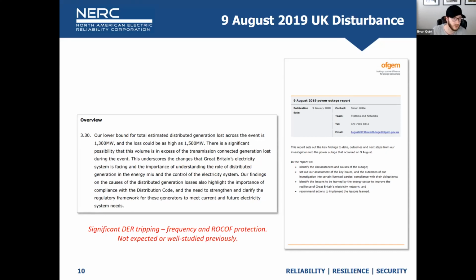And pulled right out of the report, it says our lower bound for total estimated distributed generation lost across the event is 1,300 megawatts, and the loss could be as high as 1,500 megawatts. That's a nuclear power plant sized outage across a very geographically dispersed area, right? So if that's not impactful, I don't know what is. But that was one of multiple contributors. There was a gas plant that tripped off. There was a big bulk system connected wind plant that unexpectedly tripped off. All of these things contributed to DERs disappearing as well. All of those things combined for contributors to the load getting shed. And really those tripping were caused by frequency falling, and then frequency falling so fast that it triggered certain protection schemes within those DERs.